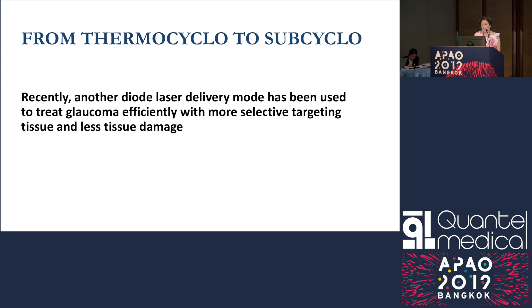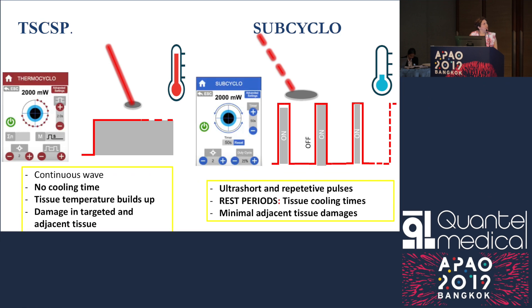Recently, another laser — the SubCyclo — has been used to treat glaucoma efficiently, with more selective targeting of tissue and less tissue damage. In contrast to the conventional thermo-laser, which delivers a continuous high-intensity energy, SubCyclo delivers ultra-short and repetitive pulses on the order of microseconds, corresponding to a time-on followed by a long cooling time corresponding to time-off. This allows the energy to cool down between pulses and avoids any coagulative necrosis in the tissue.